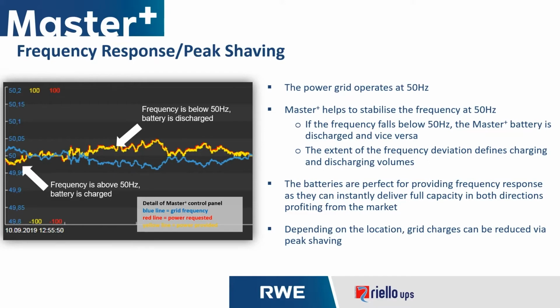Now obviously this operates in two directions. So as we can see, as the blue line increases, the demand on the system decreases and therefore we extract power from the grid and push that power into the connected batteries. However, should the frequency decrease, we then push the energy from the batteries back into the grid and therefore help stabilize the frequency. So effectively, the system is continually taking power from the grid when necessary and feeding power back into the grid when required, so that the grid maintains a stable frequency.